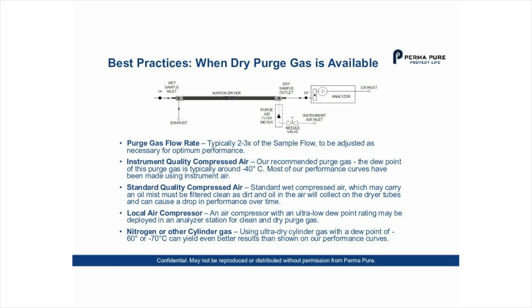I recommend going back to the first point: adjusting your purge gas flow rate. If you have an application where you don't need to get the sample as dry as the dryer can achieve, consider reducing your purge gas flow rate to save costs. We've recently found that you don't necessarily need an ultra-dry purge gas to get good performance. In some instances, a purge gas dried to minus 10 or minus 15 degrees C has proven effective enough to dry the sample to the level the customer needs.